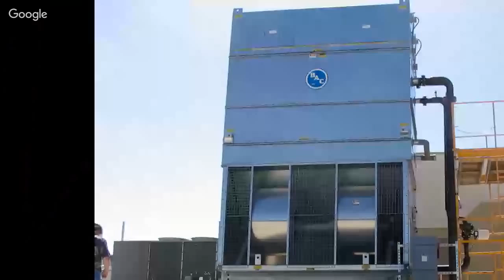Let's say you don't have a district cooling system or a big chiller plant in your building, you have a smaller building. You can implement what's called a process cooling tower, where it's basically just exchanging energy with the air. These are two big fans blowing air across a coil, and that coil is the process water going to your equipment. This one is a fluid cooler, so it actually sprays water up here to do evaporation across the closed loop cooling coil to get more efficient heat exchange.